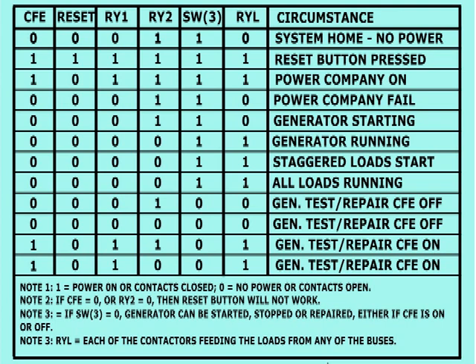This brief truth table shows the logic states of the different voltages and closed contacts, detailing the operation starting with the circuit breakers turned off, thus simulating a blackout. Then after turning the breakers on, simulating power company AC is back, the reset button is pressed, which locks the RY1 contactor, thus feeding power company voltage to the corresponding bus. The next step is when a blackout occurs, with which RY1 is released, being totally insensitive to any temporary flashback of the power company voltage.